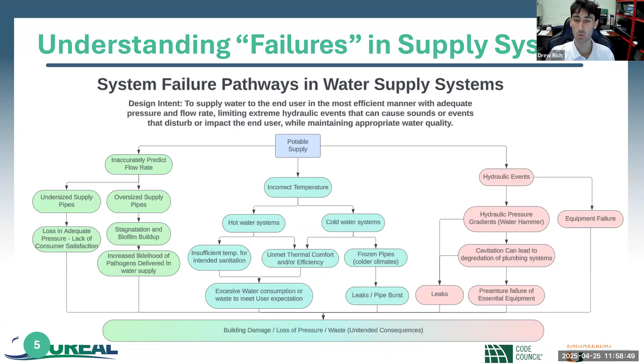We talked about inaccurately predicted flow rate, but incorrect temperature can lead to a lot of different unintended consequences, like unmet thermal comfort and/or efficiency, insufficient temperature for sanitation, frozen pipes, leaks, bursts, excessive water consumption, right? So on the other side of things, we have hydraulic pressure gradients, right? So water hammer events that can lead to equipment failure. Through identifying all of these failure criteria, we can then start to understand what we need to standardize in order to create data sets that are more available and more affordable. Okay.